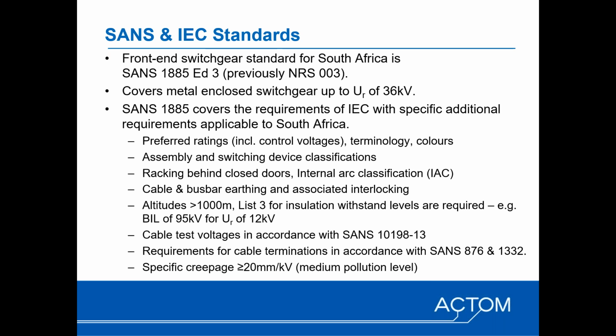For example, the termination of 3-core cables into switchgear, which is still very common in the medium voltage environment. The standard covers metal enclosed switchgear up to 36 kV. Examples of what 1885 would cover would be preferred ratings, including, for example, the control voltages, 110 volt DC, 30 volt DC for mining applications, and so on. Some of the terminology used, for example, bus section breakers versus bus couplers, as well as preferred colors for switchgear assemblies. It covers assembly and device switching device classifications.